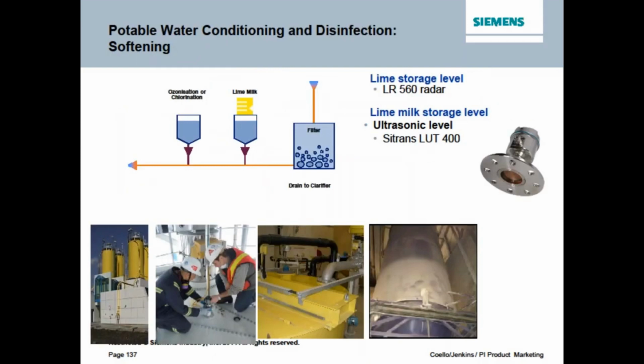If you're dealing with any sort of granular application, be it in a water plant, a lime tank, or any sort of power plant that might have pebbled lime or hydrated lime, that's always going to be a radar application, and you're going to want to use a high frequency radar there. Again, you're typically dealing with very tall, very narrow silos, so we want that really tight beam angle and aiming capability.